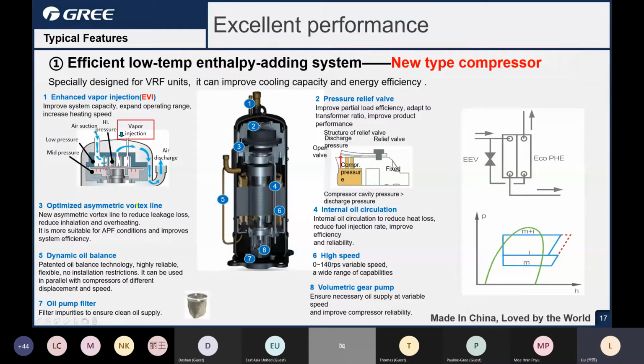The third one is about the vortex. The vortex line. We use this new compressor, and this is the built-in advantage of this compressor. Another one is the internal oil circulation. You can see here there's an oil circulating pipe in the compressor. So if there is too much oil or too little oil, this pipe will return or discharge the oil to circulate in the system and make sure the lubrication of the compressor is good.